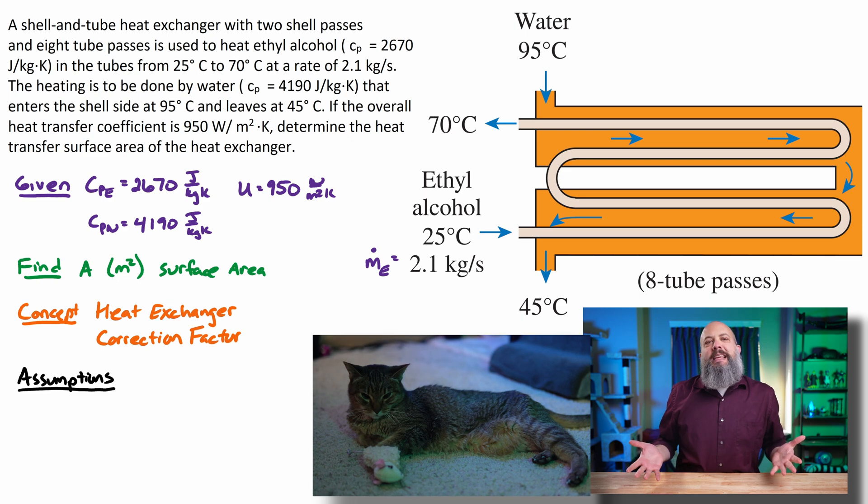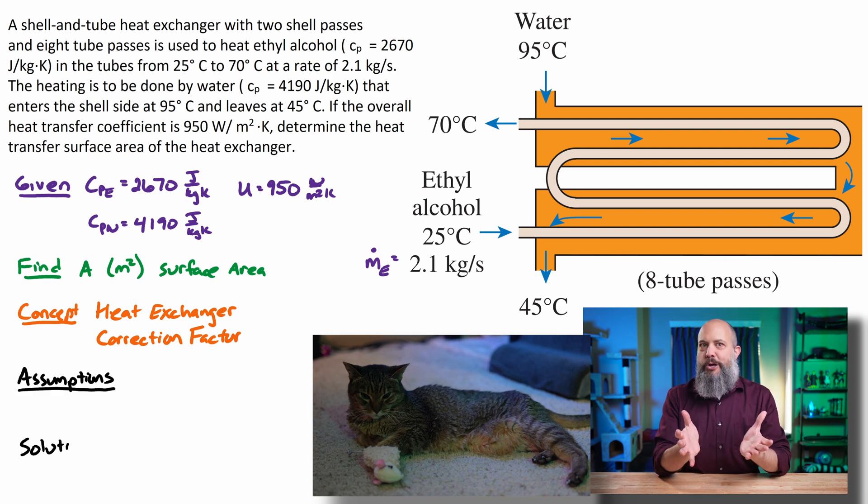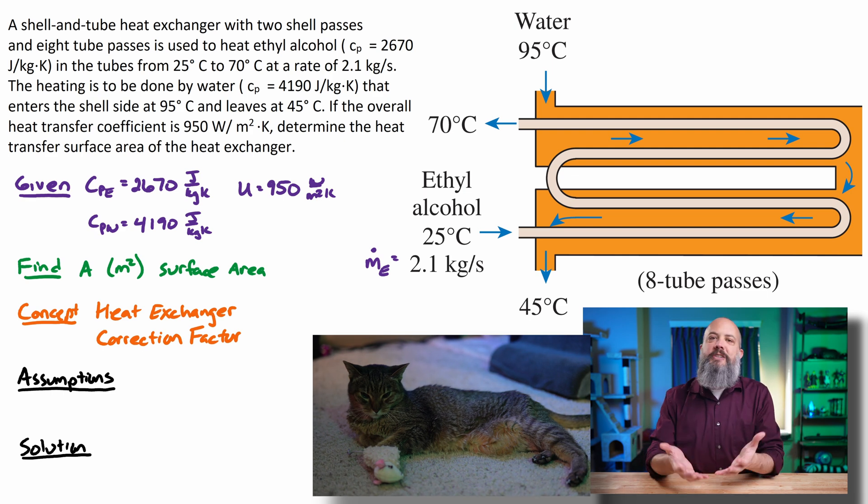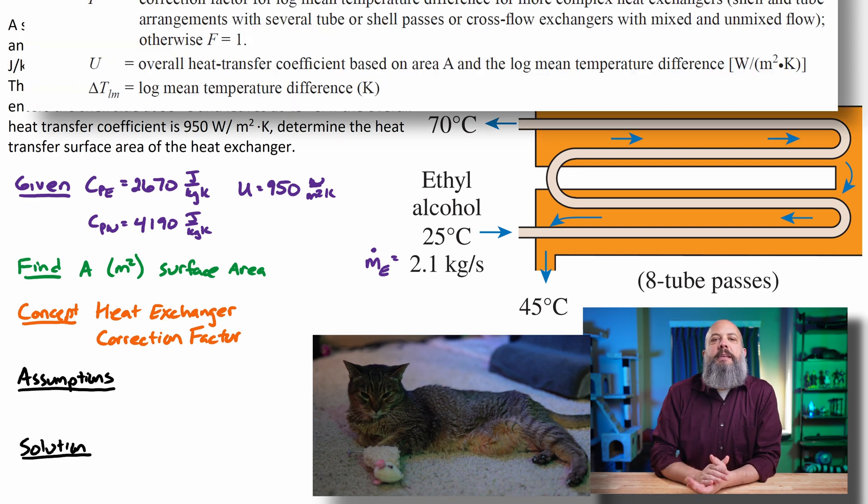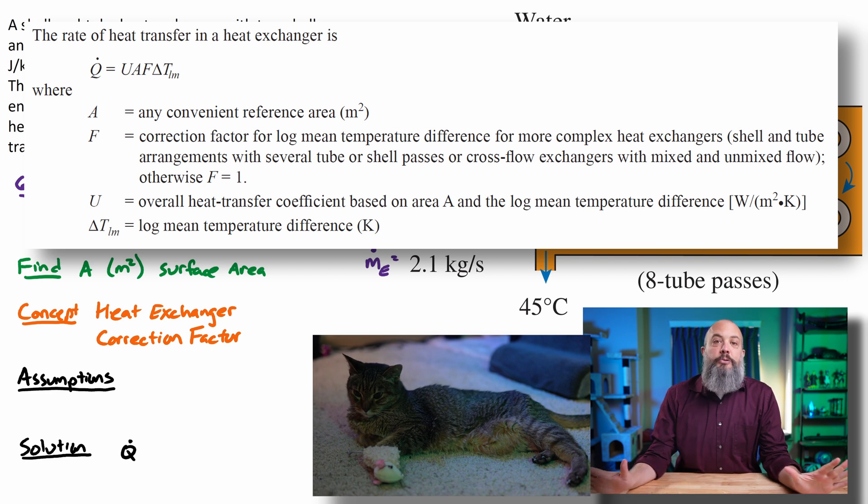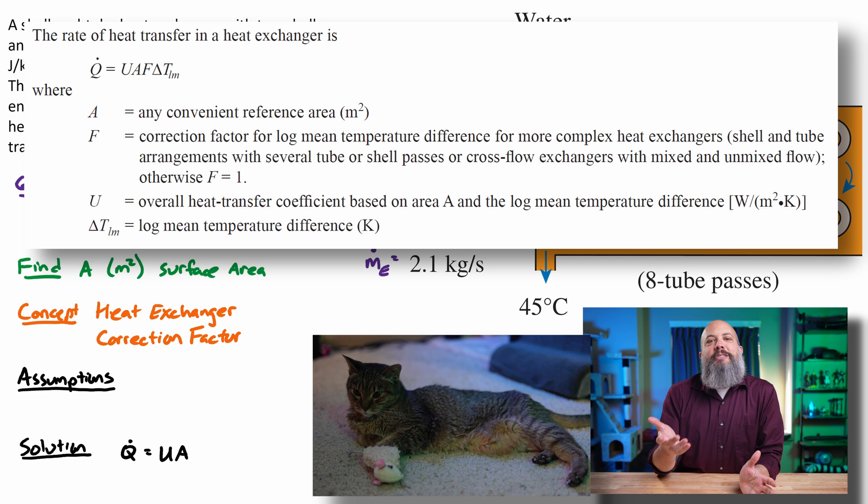Shell and tube heat exchangers are going to be a little bit different than regular parallel or counter flow double pipe style heat exchangers in that you need to apply a correction factor F. You'll still use the same main equation.